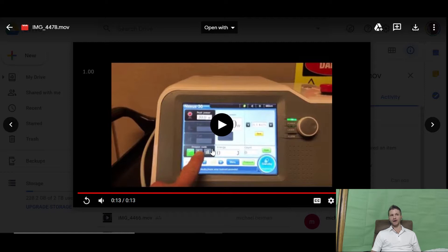In terms of raw power, what is coming out of the hand piece with our Nexus here? It's the same — a full 30 watts of max, and you can obviously adjust that power level. Now you're thinking: this is an old laser — how do I know if it's good or not? Hold your horses. Any laser we get, whether it's a year old or two months old, it really doesn't matter. We send it down to a laser company in Florida — we can send you that info. Including third-party testing with a beam meter and a lot more gear, we assess the actual output power of the hand piece, the actual output power coming out of the diode internally. We test all the important optronics inside the module to ensure the laser is putting out what it should be. We can even assess things like diode life. So when you're buying that laser from us, you know what you are buying.